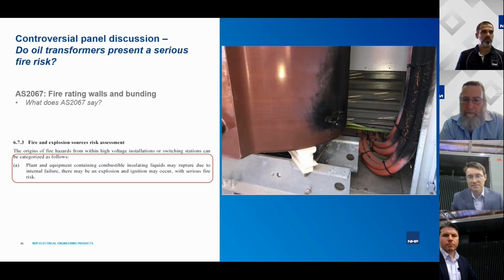This is why we can see there is a bit of black carbon around, but that was the result of that initial electrical arcing fault, and nothing really happened after that. You can even see the cables near the transformer, they're still intact down the bottom. Therefore, there was not any fire going on after the electrical fault. So that's a key difference between oil and cast resin, and it is well reflected in the AS2067 standard with regards to installation requirements, where the fire protection and fire clearance requirements for cast resin transformers are significantly less than for oil transformers. And yeah, you can read the standard for details.